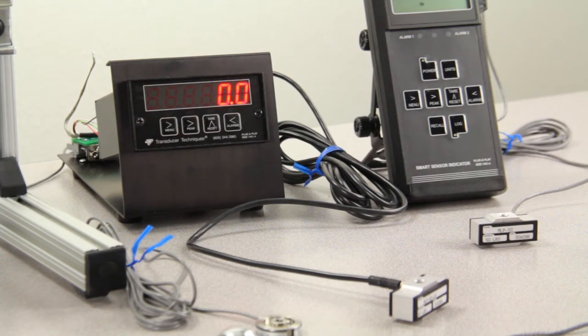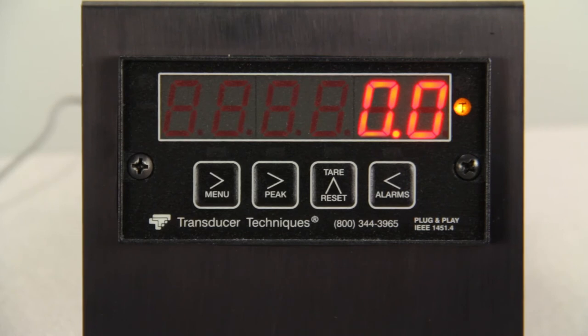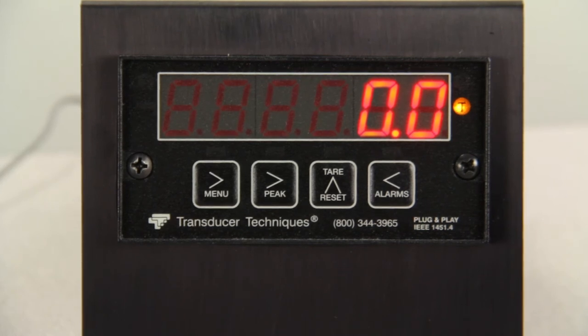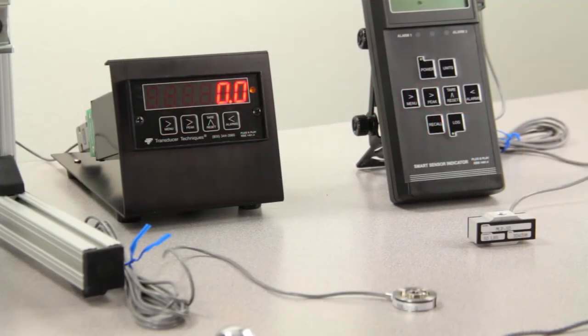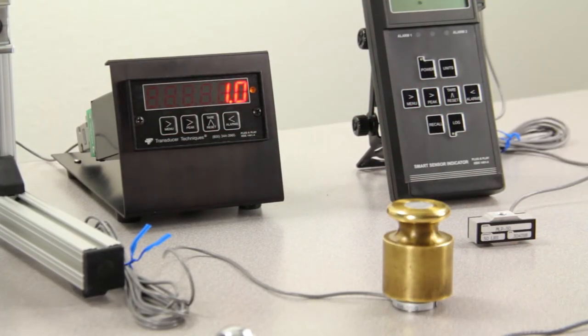Now let's do the same test with the smart plug-and-play option. The yellow light on the right hand corner is indicating you have a smart plug-and-play load cell connected. Let's put that same 1 pound weight on the load cell. Notice the meter's reading 1 pound. You're calibrated and ready for use.